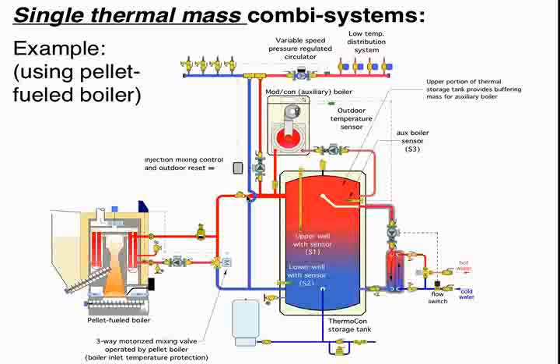As far as the life on other tanks, tough to say. Some of the EPDM linings that are out there, typically you hear numbers like 15 to 20 years, and then it's a new liner. One of the things I would add on that, and just a little plug for the thermocon too, is you want a tank, like Siggy mentioned earlier, that's insulated completely. I know some of the other tanks that are out there don't have the 2 inches of foam completely around. Our tanks are foamed on the top and injected foam, so you've got that 2 inches on the top and the bottom and all around it, so you don't have that loss out the jacketing through a little thin piece of fiberglass or something that they typically use on some of the other tanks.